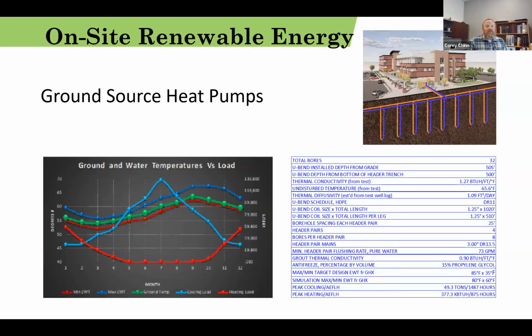On this project, we did use a closed coupled ground source heat pump system with water to air heat pumps that are distributed throughout the building. So as you guys all know, the beauty of heat pumps is we're able to share heat around the building. So in this building, we have a long east-west axis. So we have a good southern exposure, a good northern exposure. We have quite a bit of the year that we're moving heat from the southern side and putting it into the north side. And the building works beautifully.